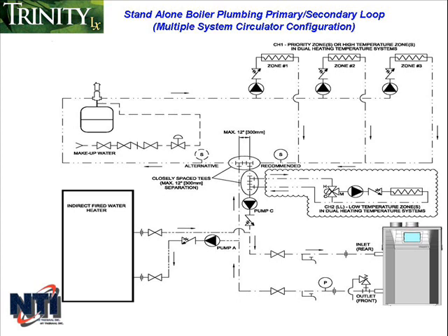The advantage, however, is that if only the low temperature zone is calling, the boiler will deliver water temperatures to match the requirements of the lower temperature zone. So, instead of always generating water temperatures that exceed the requirements, then mixing it back down, when just the low temperature zone is calling, the boiler will only deliver the low temperature. So less energy is spent heating water to higher temperatures just to mix it back down, and the boiler will get better efficiencies by having a lower return temperature and getting more condensing.